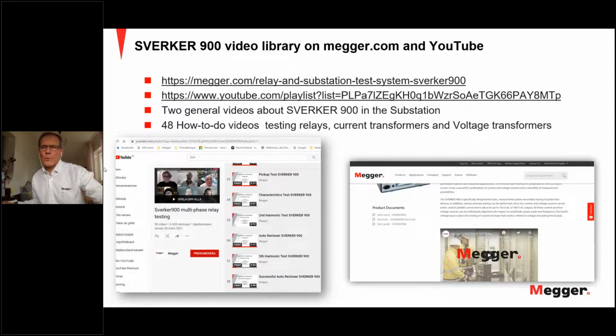So another question: is it possible to measure the secondary winding resistance of a CT by using the auxiliary variable DC generator of a Sverker 900? If they're speaking about making burden tests and so on, this is possible to use a Sverker for doing these kind of tests. We can do all the tests on a current transformer with the Sverker 900.